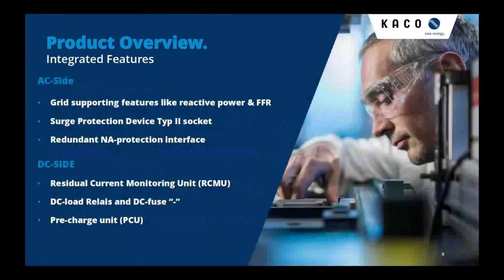As I said, we have integrated features. On the AC side, we have grid supporting features like reactive power and FFR. We can also integrate surge protection devices of type 2. All of our inverters have a redundant NA protection interface, an inverter-off interface. On the DC side, we have a residual current monitoring unit (RCMU), DC load relays, a DC fuse, and a pre-charge unit.